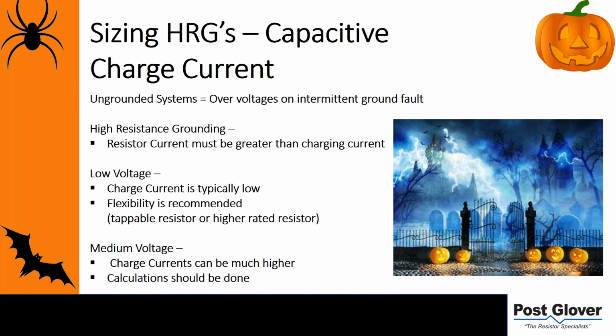Essentially, capacitive charge current is in every system you can think of. It doesn't matter what type of electrical system, you're going to have capacitive charging current. What that is, essentially, is leakage current that naturally exists because there's naturally existing capacitance. If you look at the definition, you have two conductors with an insulator in between—that describes a capacitor. There are naturally occurring things like motor windings, parallel cables, all types of things in your system that have these naturally occurring capacitances. That capacitance carries a charge, it carries current. So you're going to be having that naturally leaking current.